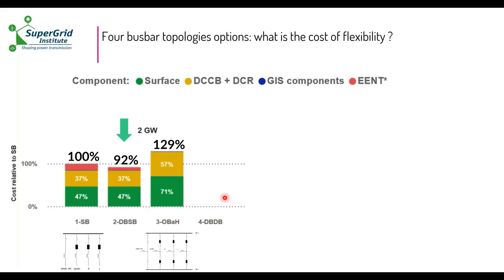these 3 topologies here are all compliant with AC stability constraints, so you can compare them. And depending on the topology, you will have more or less expected energy not transmitted. You will see that the yellow one and the green ones are similar, but since you allow less energy curtailment in the double bus bar single breaker here, this one will represent a TOTEX reduction of 8% with respect to this reference value.